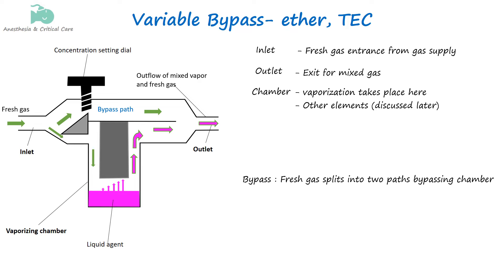The reason it is called bypass is because the vaporizer has a bypass pathway that allows a portion of the fresh gas flow to bypass the vaporizing chamber, while another portion passes through the chamber to become saturated with anesthetic vapor. It's variable because the dial controls the concentration by adjusting the ratio of gas through the chamber versus the gas that bypasses it.